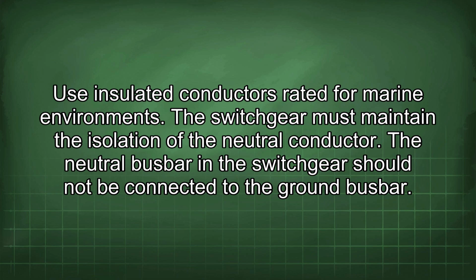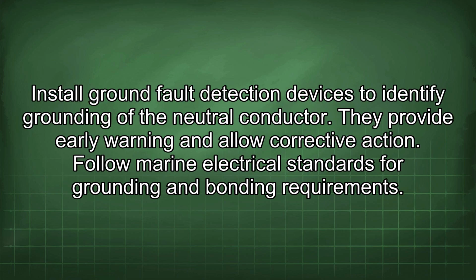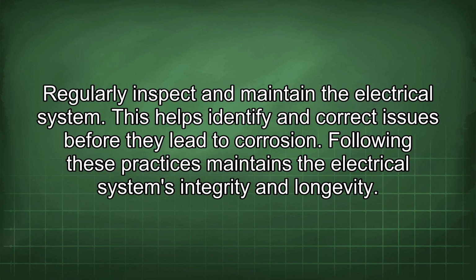The switchgear must maintain the isolation of the neutral conductor. The neutral busbar in the switchgear should not be connected to the ground busbar. Install ground fault detection devices to identify grounding of the neutral conductor. They provide early warning and allow corrective action. Follow marine electrical standards for grounding and bonding requirements. Regularly inspect and maintain the electrical system. This helps identify and correct issues before they lead to corrosion. Following these practices maintains the electrical system's integrity and longevity.